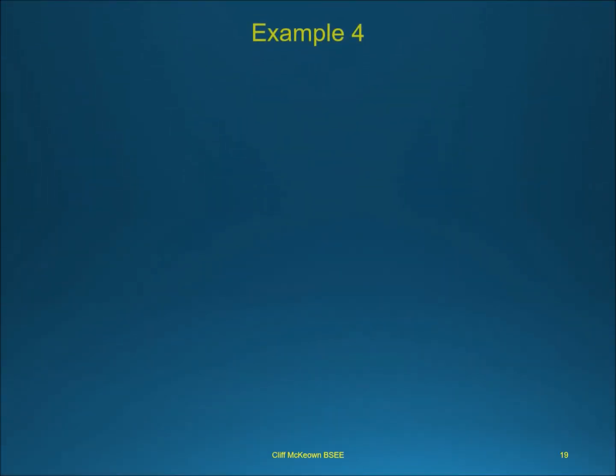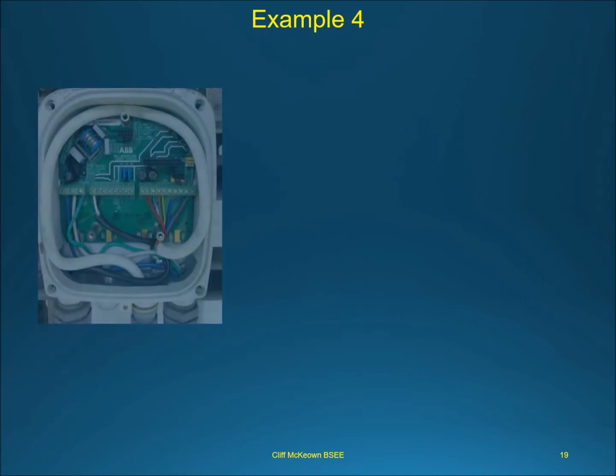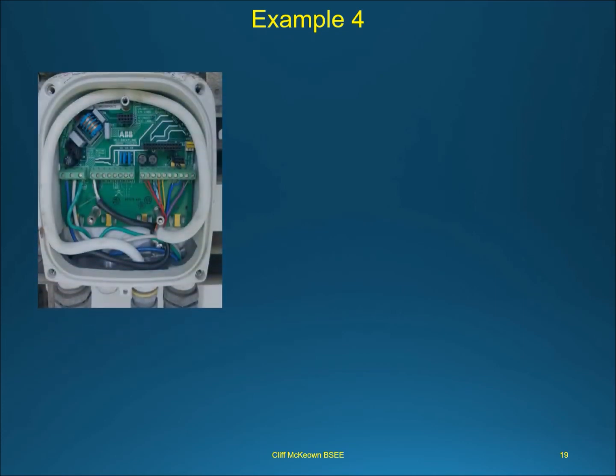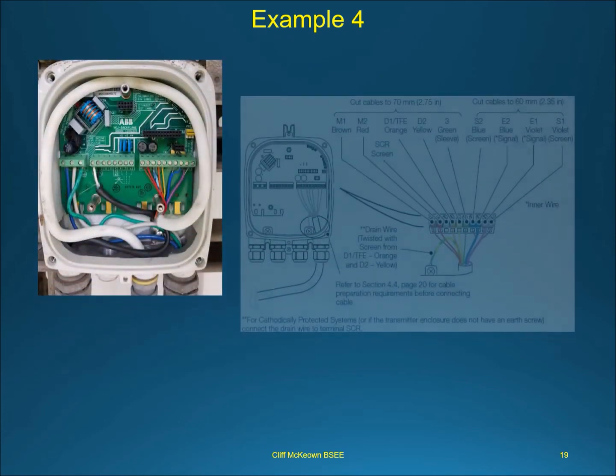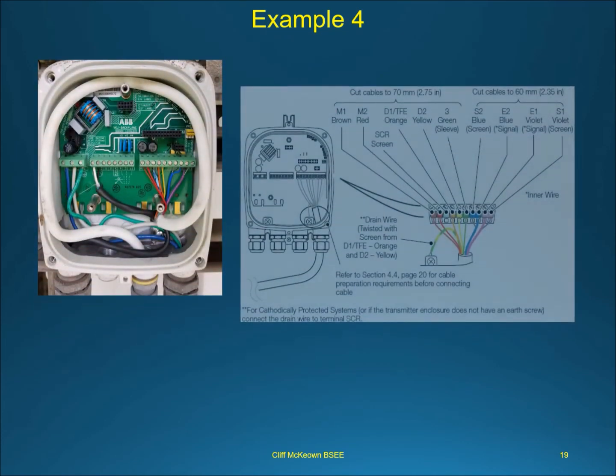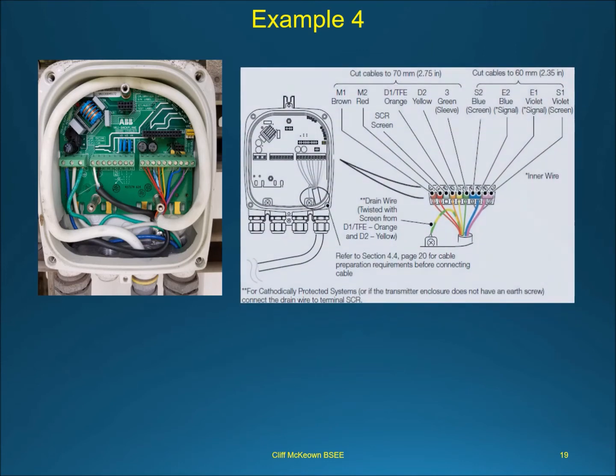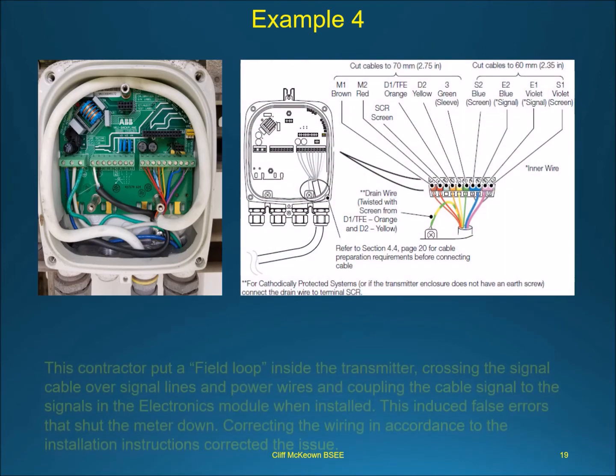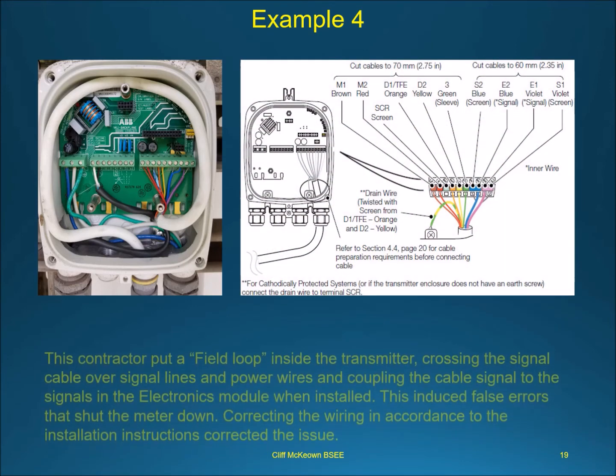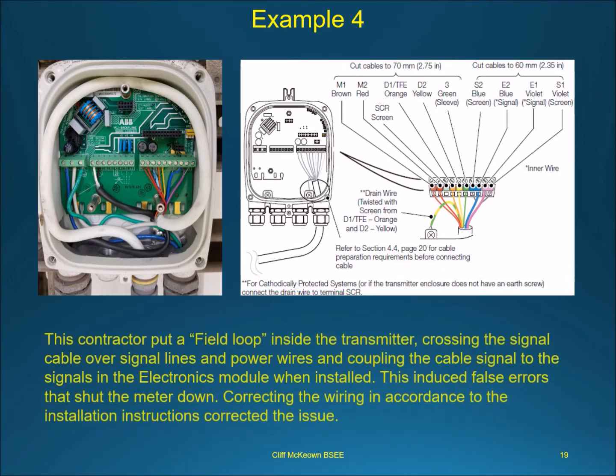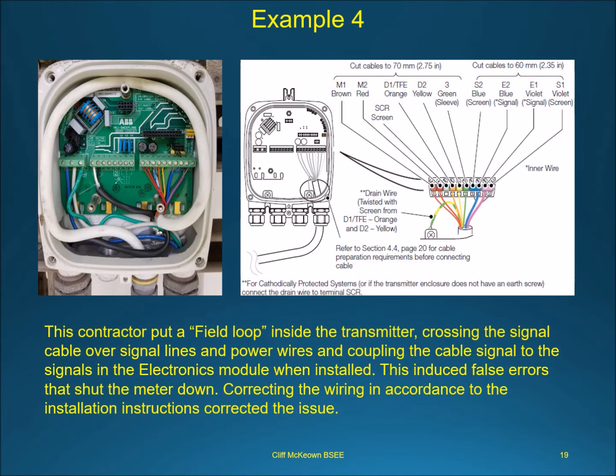This contractor put a field loop inside the transmitter, crossing the signal cable over signal lines and power wires, coupling the cable signal to the signals in the electronics module when installed. This induced false errors that shut the meter down. Correcting the wiring in accordance with the installation instructions corrected the issue.